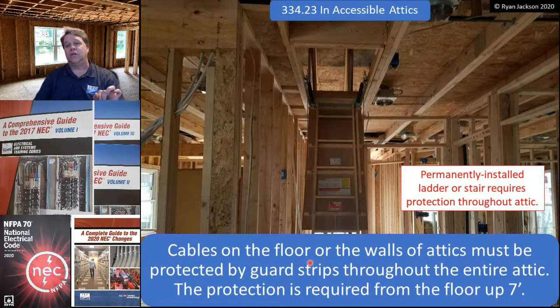And that protection extends from the floor of the attic up vertically 7 feet. The 7-foot dimension is a vertical dimension. The whole attic has to be protected if you have permanently installed stairs or ladder. So if I can get up there, every stitch of wiring in that attic has to be protected from the floor up 7 feet. I always read this as the 7-foot being a horizontal dimension. It's not. It's the entire attic space that has to be protected from the floor up 7 feet.